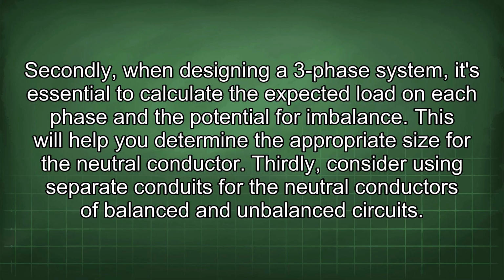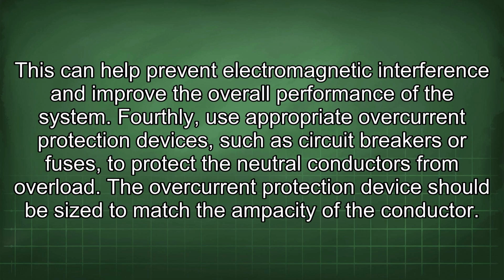Thirdly, consider using separate conduits for the neutral conductors of balanced and unbalanced circuits. This can help prevent electromagnetic interference and improve the overall performance of the system. Fourthly, use appropriate overcurrent protection devices, such as circuit breakers or fuses, to protect the neutral conductors from overload. The overcurrent protection device should be sized to match the ampacity of the conductor.